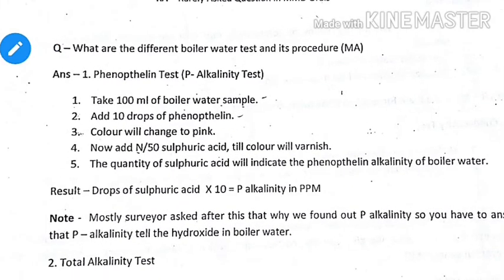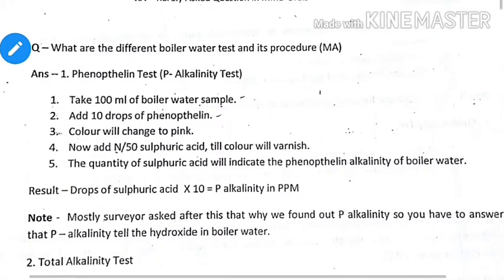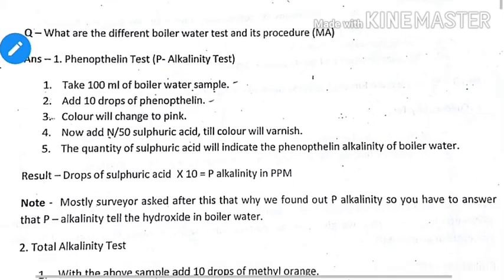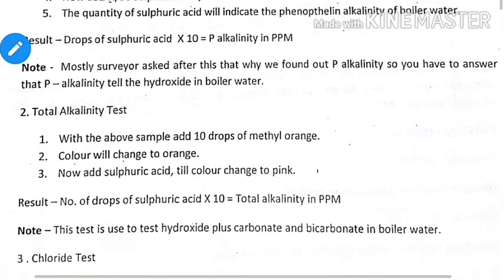To perform the test: take a 100 mL boiler water sample and add 10 drops of phenolphthalein — the color will change to pink. Then add N/50 sulfuric acid until the color vanishes. The quantity of sulfuric acid used indicates the phenolphthalein alkalinity. The result: drops of sulfuric acid times 10 equals P-alkalinity in ppm.